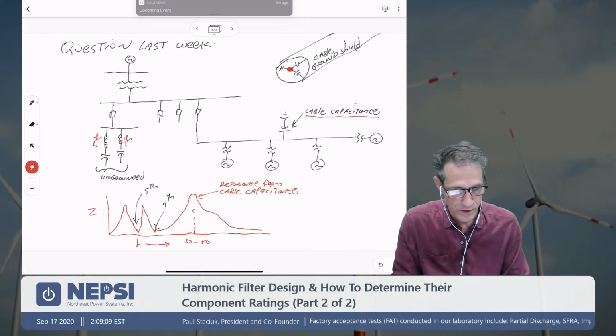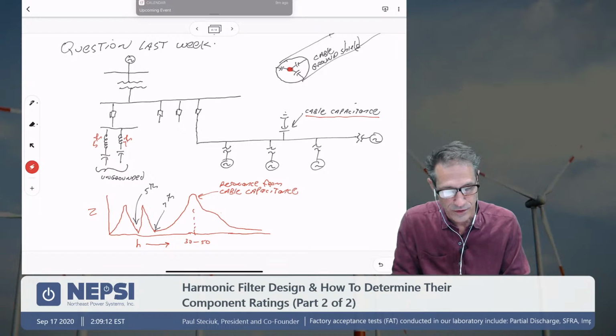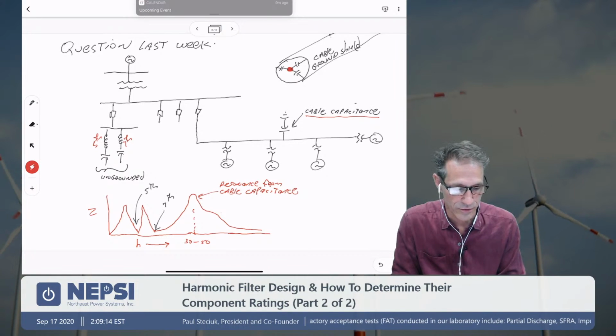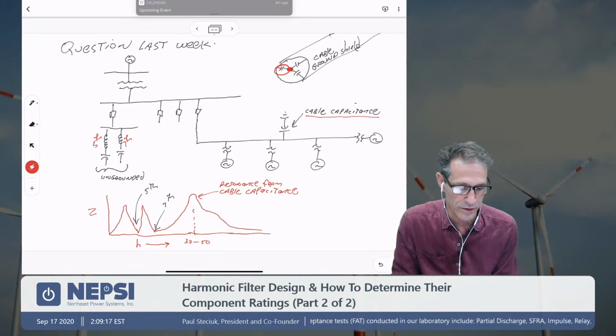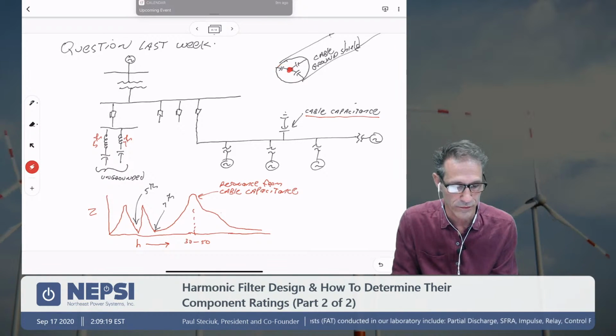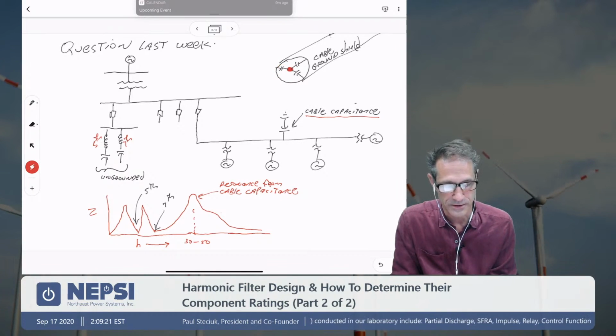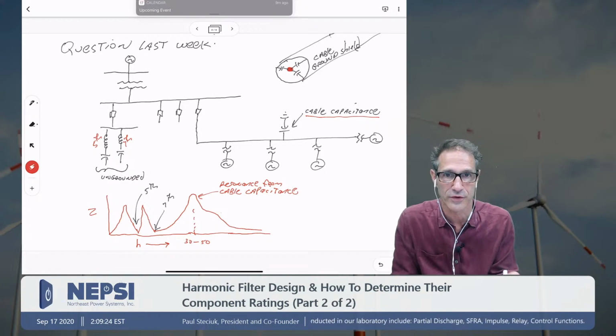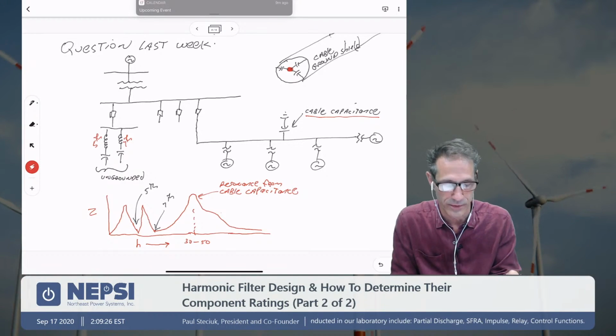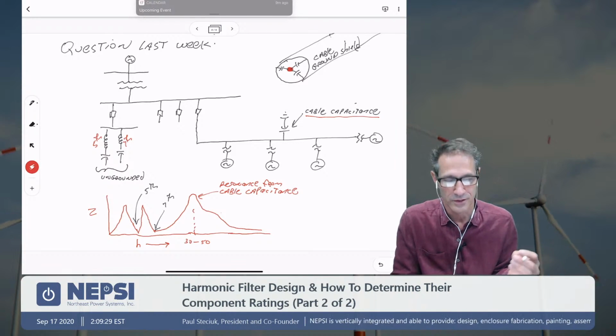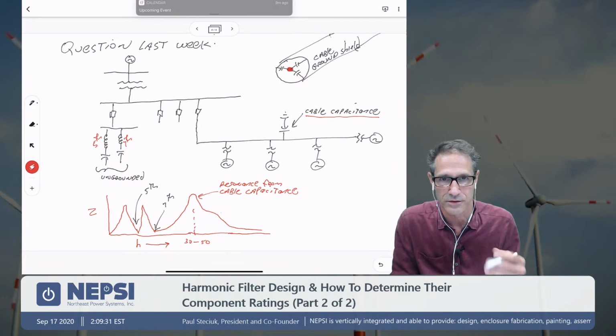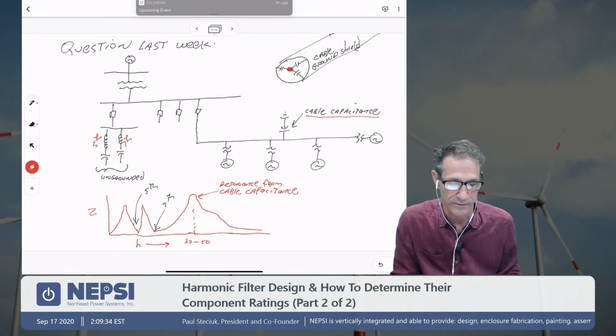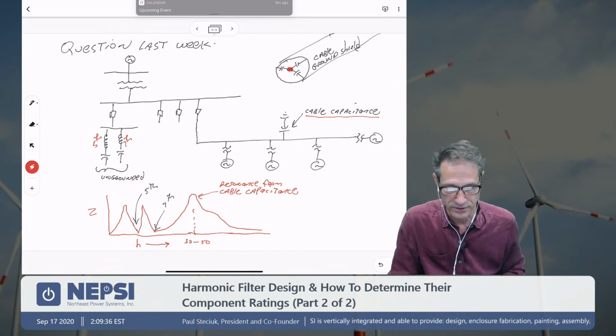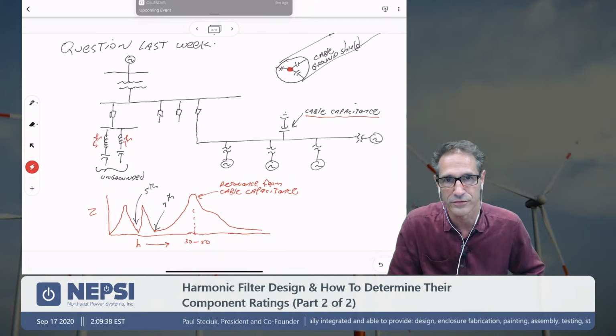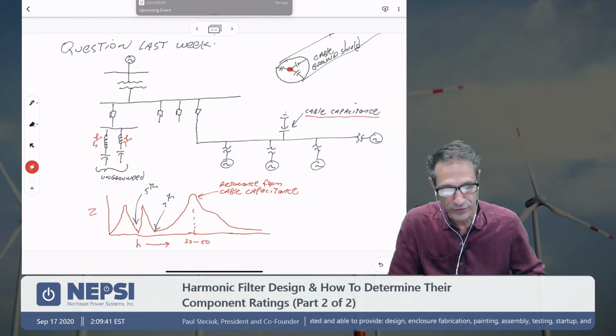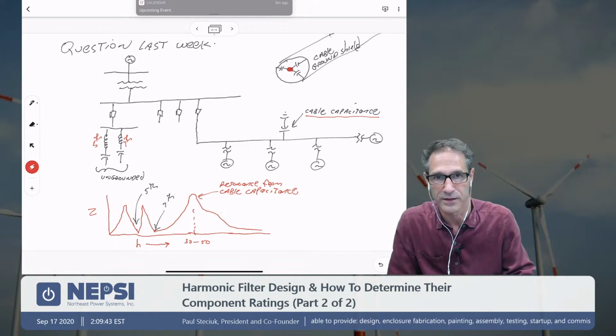And so as you know, or many of you should know, when you have a medium voltage cable, there is capacitance that exists between the inner core, the copper conductor here, and the shield that surrounds the cable. And that is a line to ground capacitance. And basically the question last week was, well, that's a line to ground capacitance. Does that enter into the positive sequence network? And the answer to the question is yes, it does.